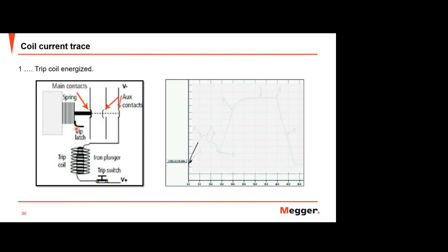So if this moves with a small force, then a higher force will move from the spring. This is just to hold the spring. So if this moves, the spring will move to the right and then operate the breaker.